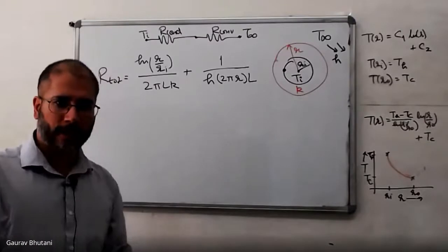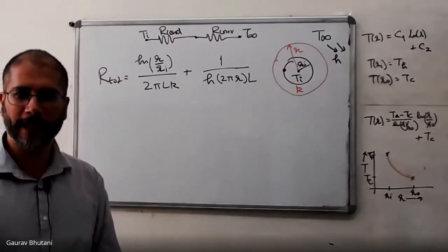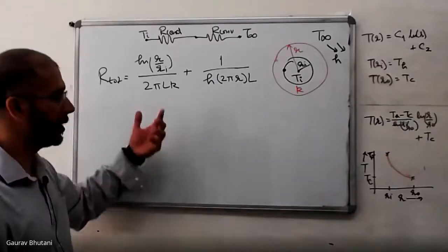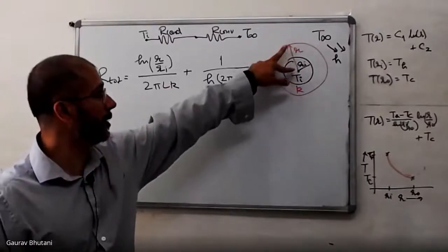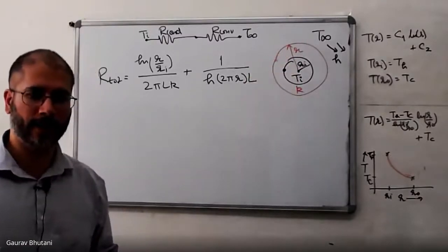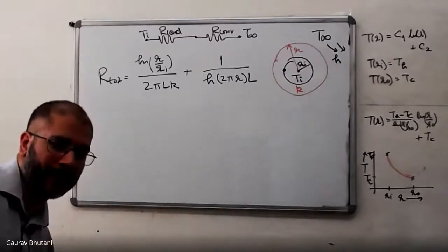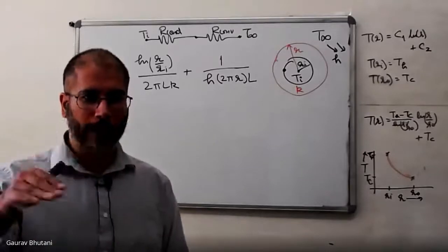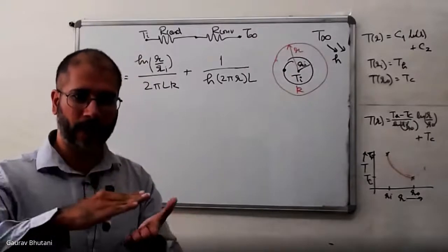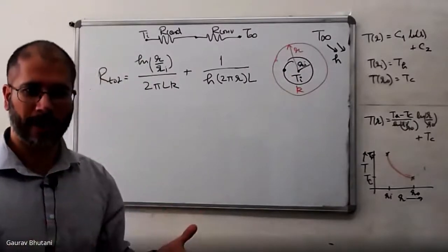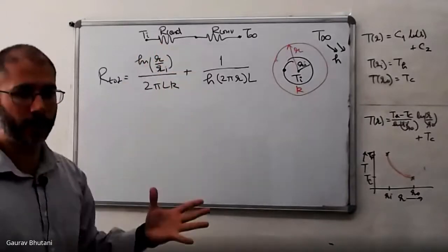Okay. So what you may end up doing is increasing the rate of heat flow. The R that you choose, the radius of the coating, which is R minus Ri in this case, has to be chosen smartly. So let's figure out how, as we change our R, that is the insulation thickness, the resistance varies. And remember, the aim is to increase the overall total resistance from what we had without any coating.